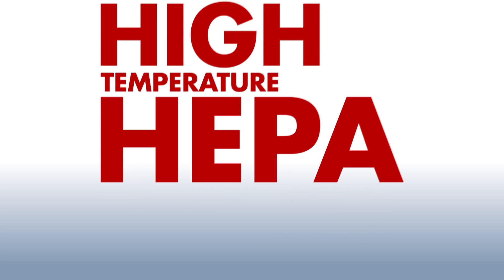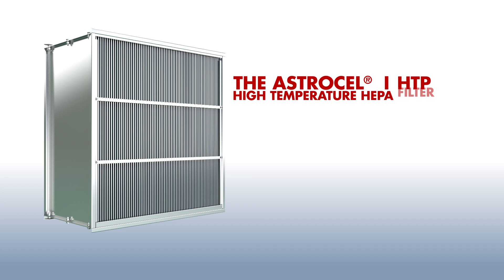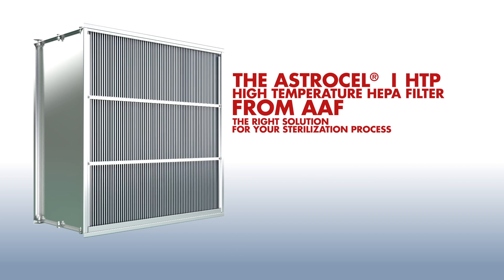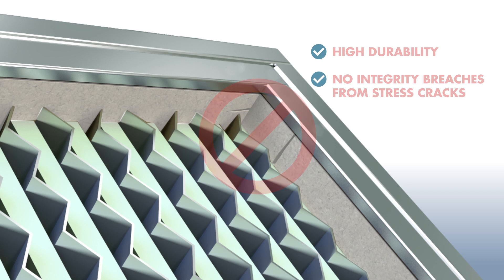Successfully answering these challenges depends on the choice of your high-temperature HEPA filter. The AstroCel I HTP high-temperature HEPA filter from AAF has demonstrated to be the right solution for your dry heat sterilization process. It provides high durability of construction with stainless steel separators and an elastic fiberglass sealant that is not prone to integrity breaches from stress cracks.